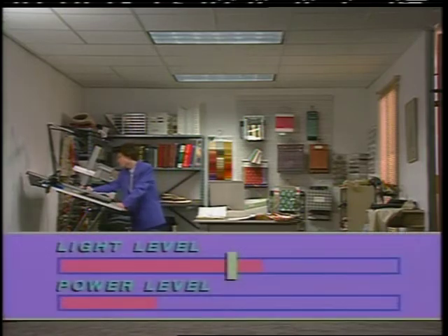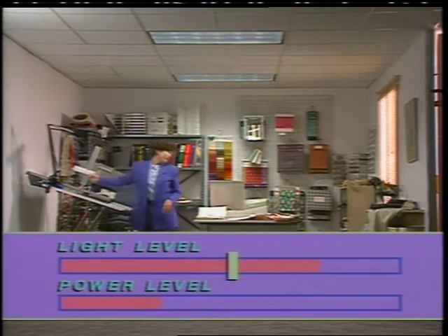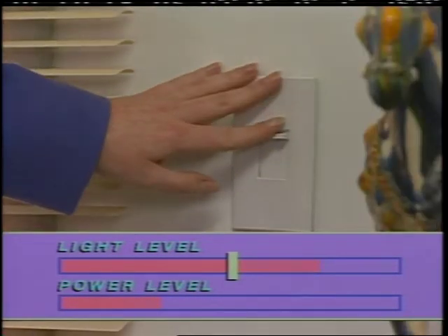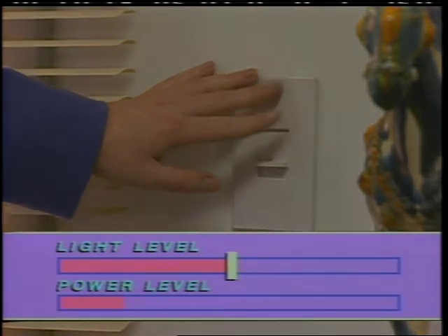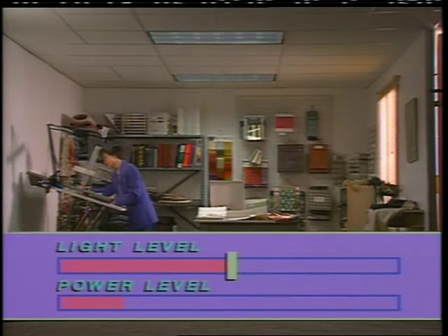This fixture can also be used with energy-efficient ballasts. A ballast modifies the electrical current to match the particular needs of the lamp. Ballasts themselves use some energy. Electronic ballasts are the most efficient type of ballast available, and many models allow dimming. This capability improves the energy benefits of daylighting.